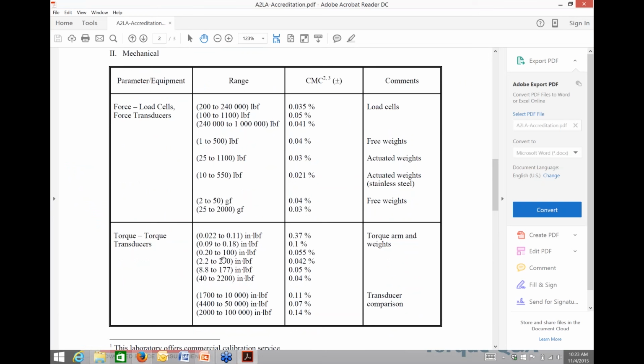At some point it jumps to different machines, and those systems have different uncertainties associated with them. So, for example, in the comparison system, we have 3 different ranges, and they have 3 different uncertainties. And again, the uncertainty is a worst case. So in this case, the 0.11% uncertainty would apply to the 1,700 inch-pound point. And then at 10,000 pounds, it would be proportionately lower uncertainty. So the uncertainty is worst case at the lowest point or applied point in a certain range. So you see we have 3 different ranges there, all done with comparisons. I hope that at least somewhat answers the question. If we had specific questions about how the calculations are performed, we could address that offline.